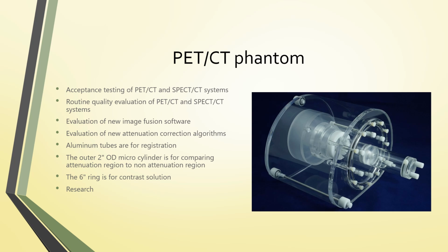Pictured here is a phantom used for acceptance testing. This has routine quality evaluation of the PET CT system. It allows for evaluation of new image fusion software and attenuation correction algorithms. It has aluminum tubes for registration, and the outer 2 inches has a microcylinder for comparing the attenuation region to the non-attenuation region. And then it has a 6-inch ring for contrast solution, and this is often also used for research.